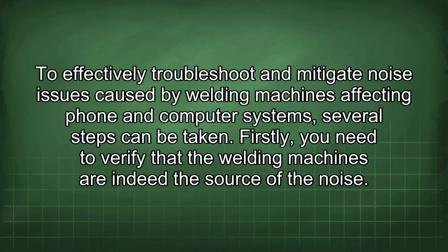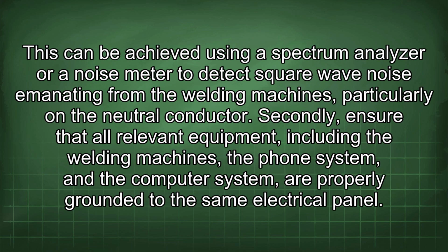To effectively troubleshoot and mitigate noise issues caused by welding machines affecting phone and computer systems, several steps can be taken. Firstly, you need to verify that the welding machines are indeed the source of the noise. This can be achieved using a spectrum analyzer or a noise meter to detect square wave noise emanating from the welding machines, particularly on the neutral conductor.